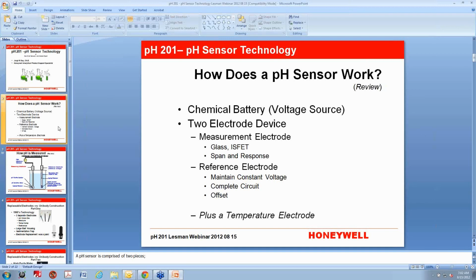So if you put your sensor in a 4 and a 7 buffer, but it only measures 4.5 and 6.5, that means that you have a short span, and that's a symptom that there's something wrong with the glass measuring electrode. It's also responsible, again, for the response. So if you put it in a 4 and a 7 buffer, it reads correctly, but it's slow responding. That is also an indication that there's some issue with the glass.